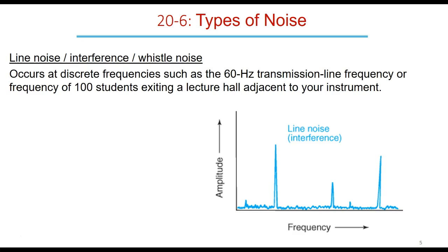Well, it's because of all this noise. It also explains why a lot of NMRs and other noise-sensitive instruments are oftentimes in separate rooms at the end of a hall, or in a basement with really thick, bunker-like walls and double reinforced floors.